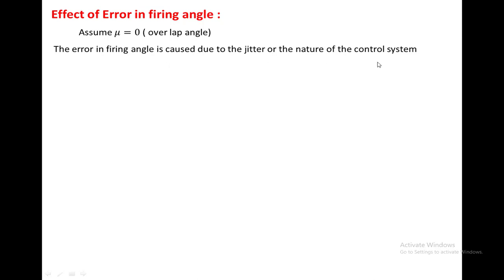Now we consider the effect of error in firing angle. Suppose there is an error in the firing angle of the converters — how does it generate non-characteristic harmonics? To analyze this, we have taken the overlap angle as zero for simplicity. The error in firing angle is caused due to jitter or the nature of the control system. There is a possibility of changing error in the control system such that pulses generated for the two converters will be different, causing an error in firing angle.